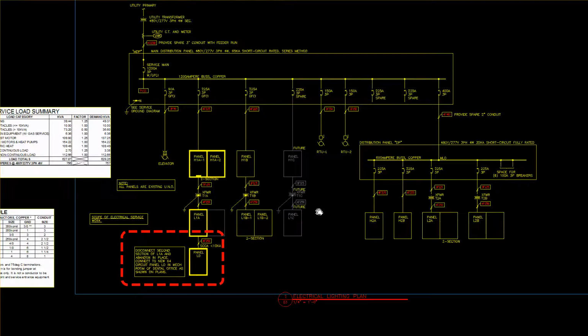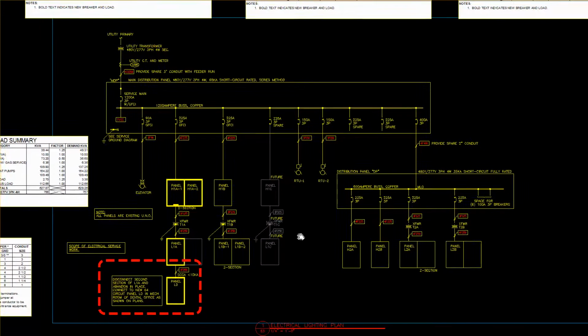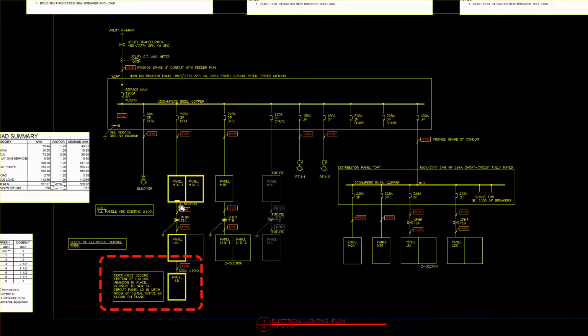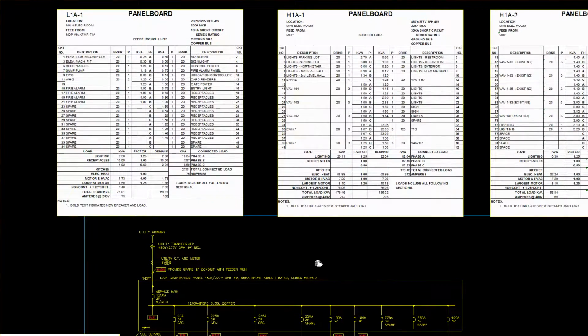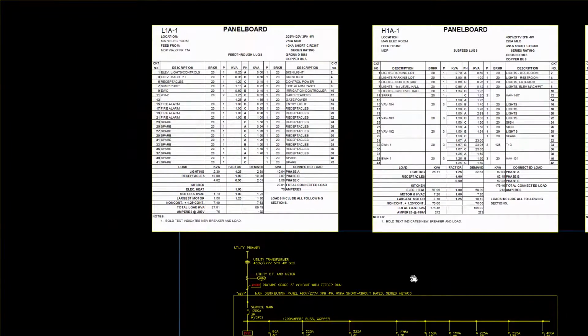In this particular one, just looking at the overarching view, you see your main distribution panel. You've got your other distribution panels, the high voltage, and then you've got this larger distribution panel over here that's 400 amps, and it's carrying a larger chunk of load out to elsewhere in the building in order to distribute your power. This particular building was about a 30,000 square foot building, and so we like to get the power out where it's utilized, keeping branch circuits as short as possible. Now let me show you a couple of panel schedules, just to familiarize you a little bit with the harmony there.